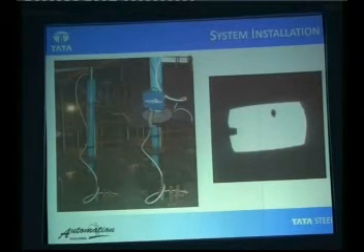Another issue with the installation is that a pinhole camera gives a mirror image, an upside down image, so we had to invert the image in the software. This system actually gives us two advantages in one installation. We have the same installation for our OptiCrop system in the roughing mill, where we cut the head portion of the transfer bar or the coil. The same camera images we use for the camber measurement also.